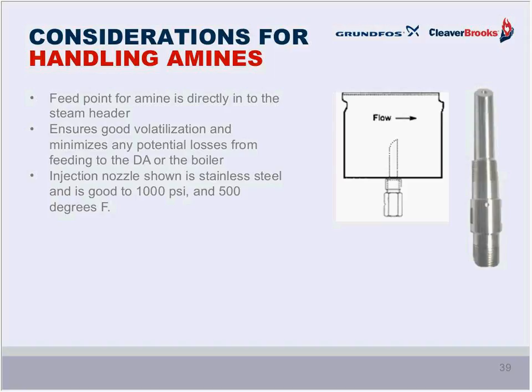In the image to the left, you see the fundamental reason for using an injection nozzle or quill. This is the part of the injection valve that is actually inserted into the pipe. Basically, you tee in an injection point because liquid will want to follow a path along the pipe wall, and so it doesn't get mixed. The quill introduces the chemical to the center of the process pipe being treated. For example, if you have a pipe that is 4 inches in diameter, you would need a 2-inch injection nozzle or quill. So, a stainless injection nozzle. Stainless is a popular choice for the amine injection into the steam line of a boiler system due to its high tolerance for pressure and temperature, up to 1,000 psi and even 500 degrees Fahrenheit.